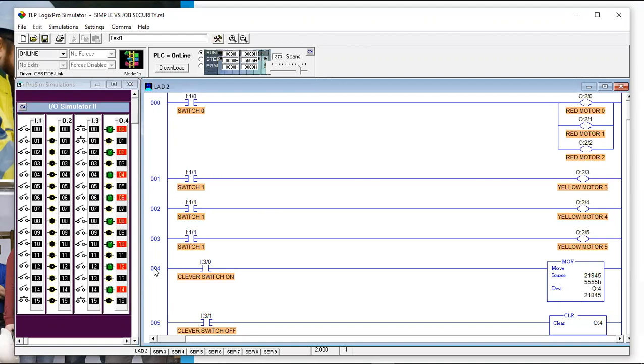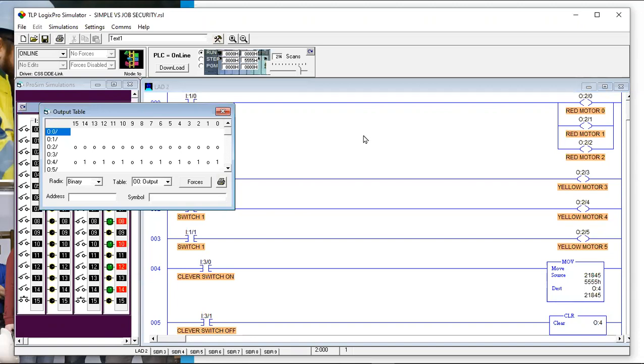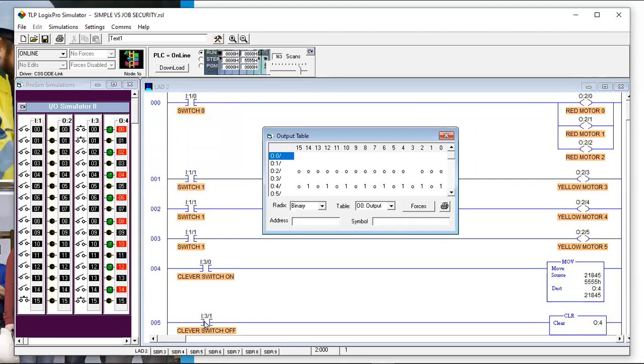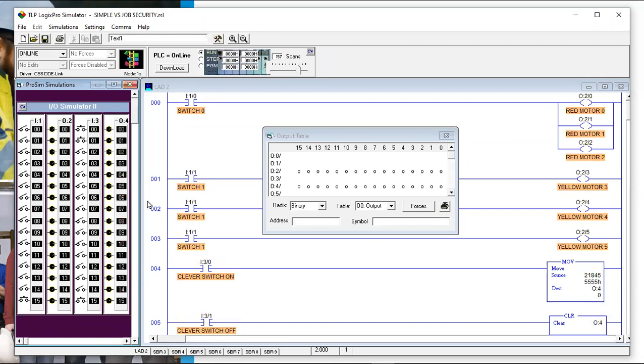We also have to be able to turn this stuff off. We have an off button, and we're clearing an entire word. Clear is a math instruction — we're saying: turn all those bits back into zeros. This is a 16-bit word and we're telling it to change all the bits back to zero. Let's watch it work: we push the off button — input three-one — it sends a clear command. We change them all to zeros, making all the outputs go off.